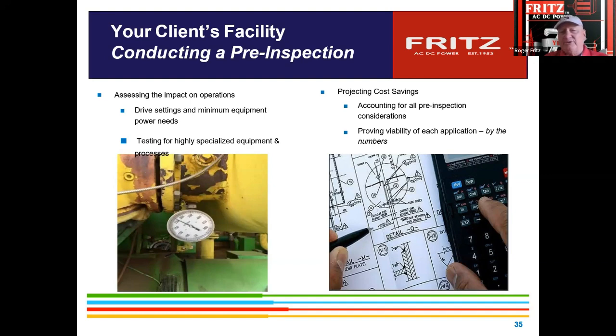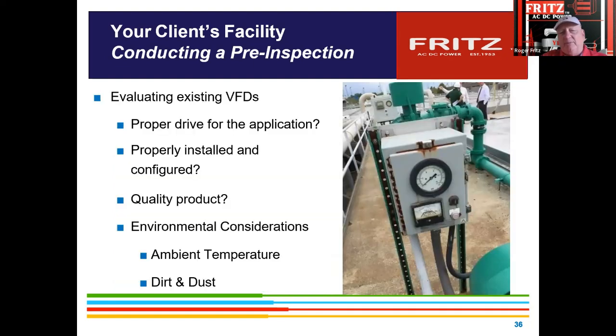Get that pre-evaluation. And then there's also a lot of extra incentive sometimes to put in what they call measurement and verification. The drive controls have kilowatt hour meters, most of them built in, so you can data log how much actual savings you're getting out of that machine and bring it back to your BMS system through various networks. They are compatible.